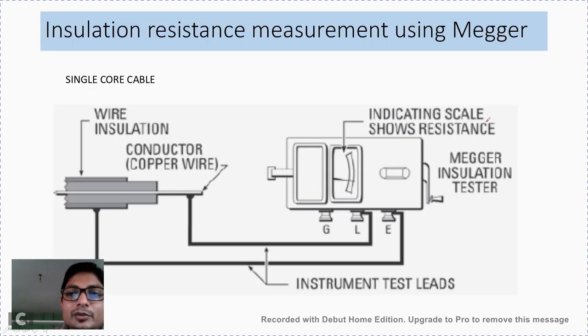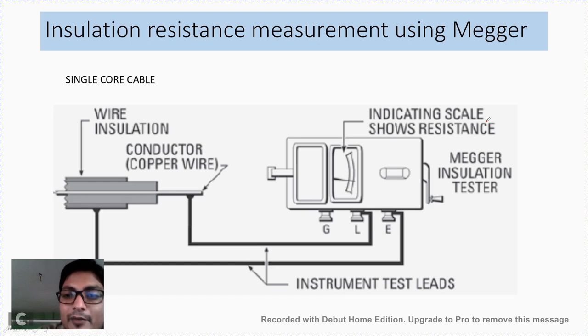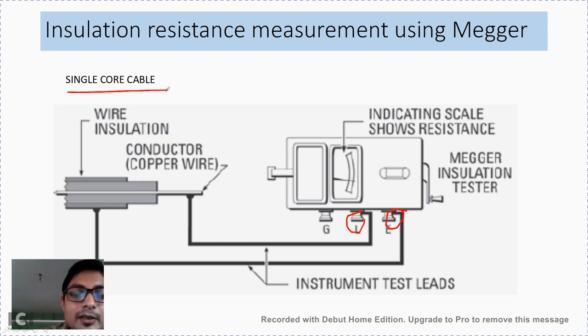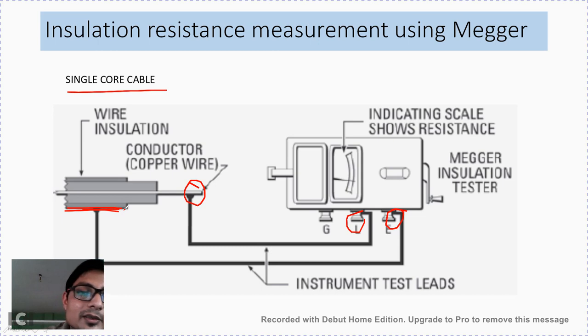The next method is measurement of insulation resistance using a megger. A megger is a hand-operated generator which generates high voltage when the handle is rotated. It has three terminals — line, earth, and guard. For a single core cable, the line terminal of the megger is connected to the conducting part of the cable, and the earth terminal is connected to the metallic sheet on the surface of the insulation.